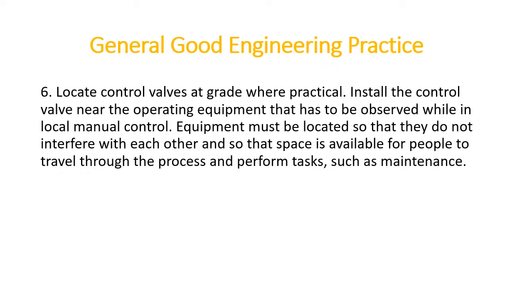Locate the control valves at grade where practical. Install the control valve near the operating equipment, so that it can be observed while in local manual control. Equipment must be located so that it does not interfere with each other, and so that space is available for people to travel through the process and perform tasks such as maintenance.